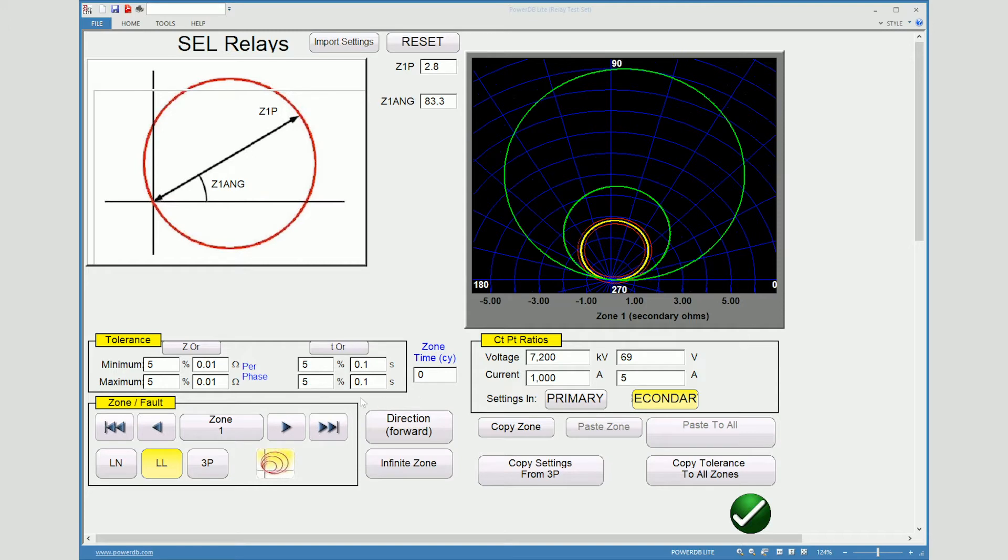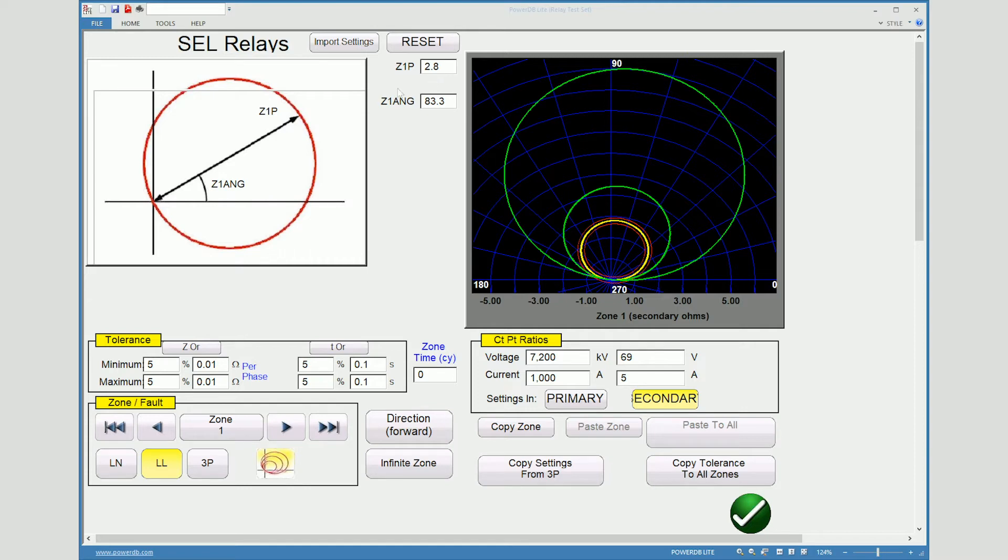Now that we have the settings input into the test program we can also verify this by having the zone one which has no inherent time delay per the settings that I have. And then also you have the 2.8 ohm at 83.3 degrees which was our setting that's in our current relay at the moment. So what we can do now is come down to hit the green check mark.